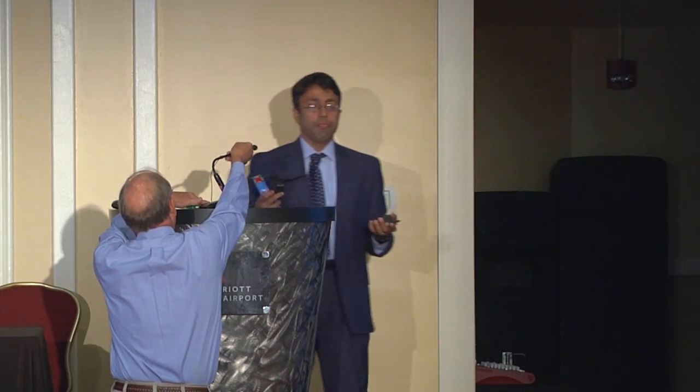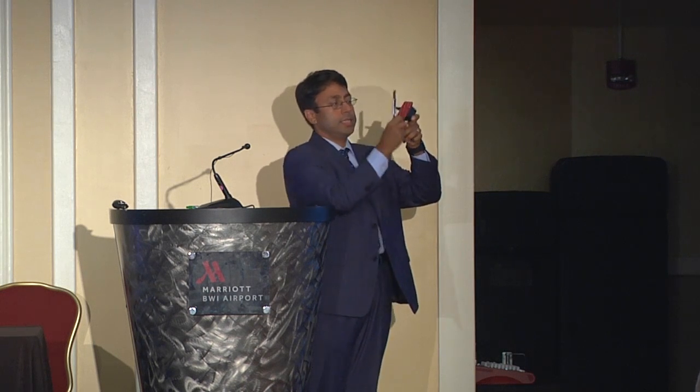We developed this technology out of University of Maryland research, and then the research spun off under a company called Resensys. These are small wireless devices designed for long-term monitoring — each has a non-rechargeable battery inside. This is a precision tilt sensor; it can monitor movement or changing orientation of a member with a resolution of a thousandth of a degree. This is a similar device for monitoring strain, with a wireless transmitter connected to the strain sensing element.